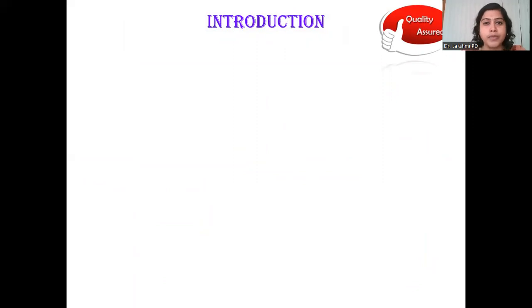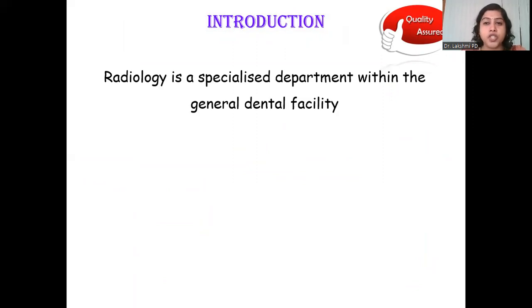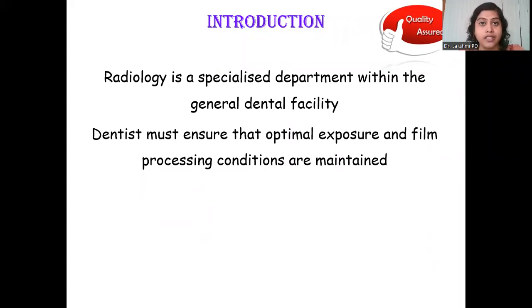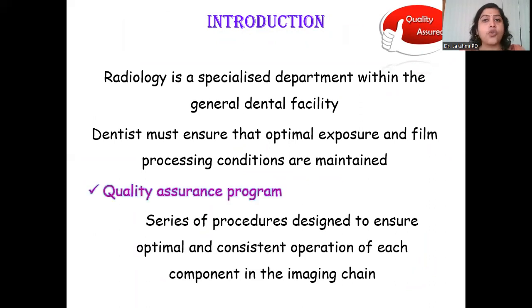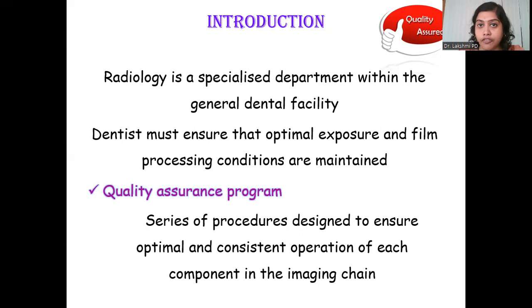So what is the need of a quality assurance program in dental radiography? Radiology is a specialized department within your general dental facility, whether it be your hospital setup or your private dental clinic. Every dentist who uses dental radiography on an everyday basis must ensure optimal exposure and film processing conditions are maintained to give consistent output of high quality radiographs. A quality assurance program is a series of procedures designed to ensure optimal and consistent operation of each component in the imaging chain, providing high quality radiographs with the least cost and least radiation exposure.